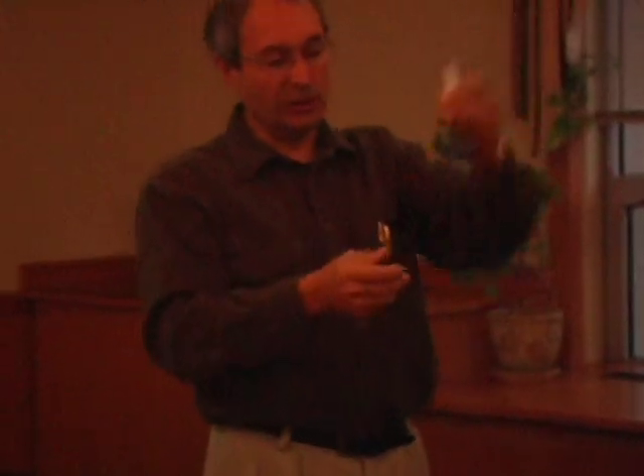Now, when we service the membrane, we would withdraw this sensor holder out from the liquid that's being sensed. We would unscrew the bottom, that's around here, there it is, to expose the membrane, unscrew the membrane, and discard the old one. This is the electrolyte. This is a cone cap. We would screw this on the top of the electrolyte.